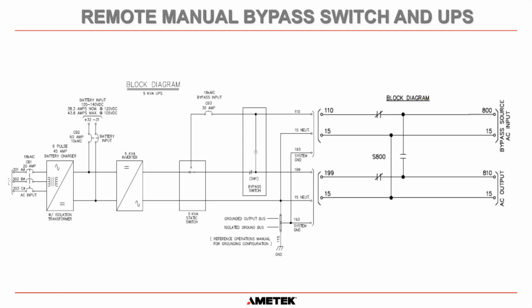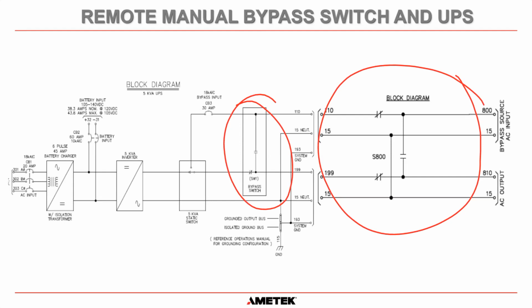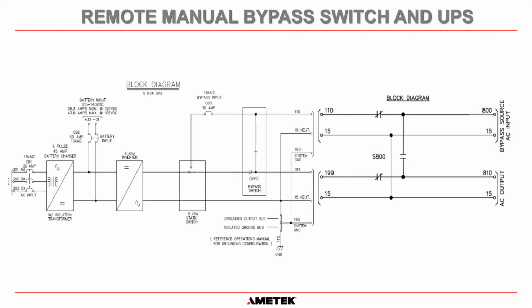So whenever we install an RMBS on a system that already has an MBS, acronyms, PWM, IGBTs, it's acronyms all day today. Whenever you have both switches, what we recommend is you go to the MBS on the UPS, unscrew the handle, take the handle off, and leave it in its normal position and forget that it was even there. It will stay in this position forever, and then we can use the RMBS to do all the switching. So the answer to your question, Cameron, is to avoid confusion, because confusion can cause load to be dropped, and that is something we don't want. Hopefully that answered your question.